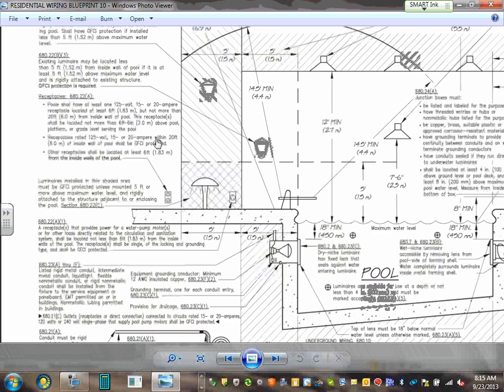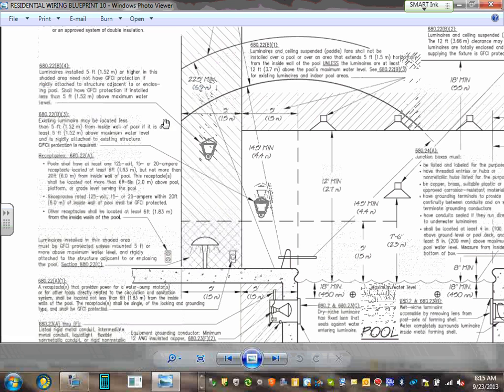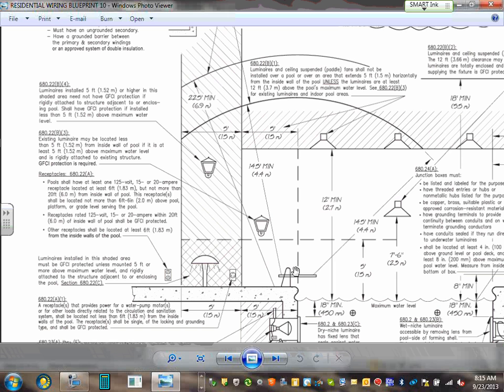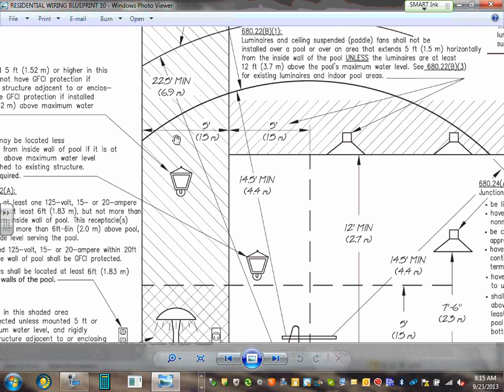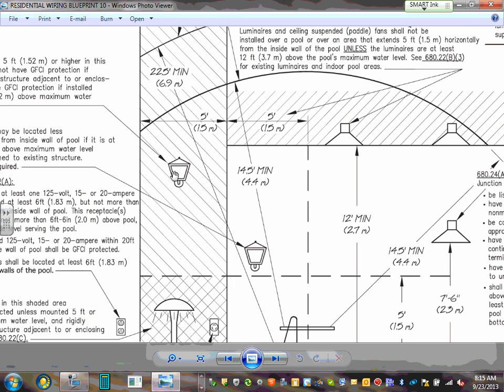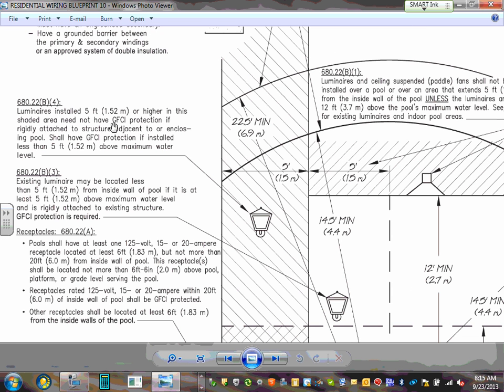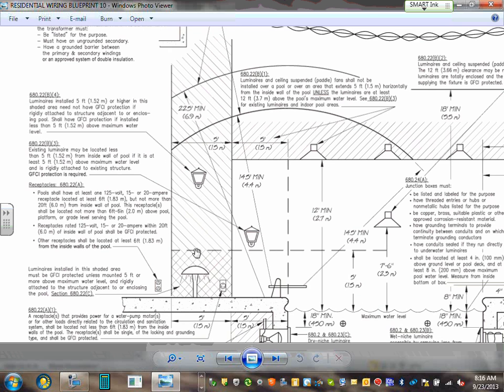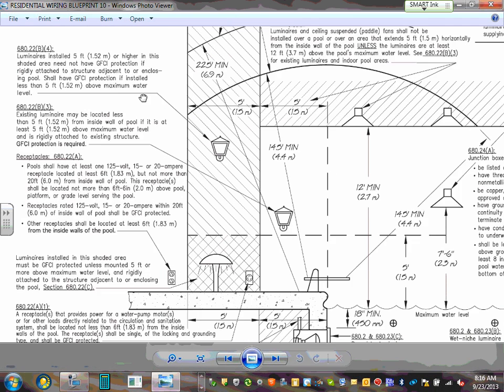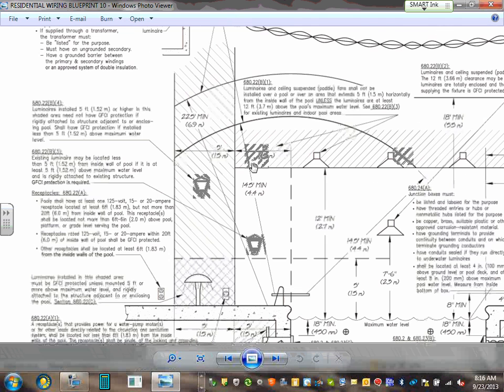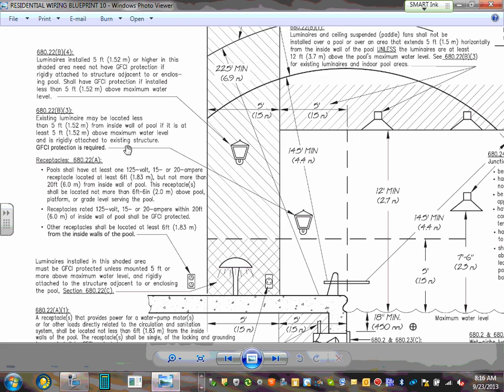Any comment, guys? Any questions? See the rules? Look at the light here. Your light here, you have to clear the distance here. You have 5 feet. You move your lights all 5 feet away. If you put it in this area here, look at the requirement. 5 feet away, GFCI protected, or higher in this shaded area need not have GFCI protection if rigidly attached to the structure adjacent to the pool. It shall have GFCI protection if installed less than 5 feet above the maximum water level. If you install it lower than 5 feet, you have to GFCI it. So there are a lot of rules, guys, in terms of where to put the light and when you GFCI them and so forth.